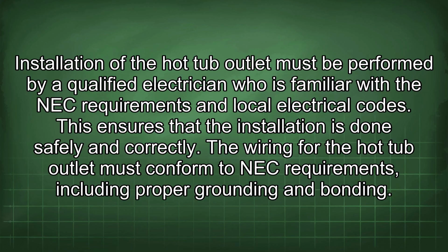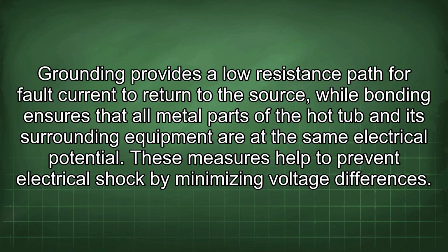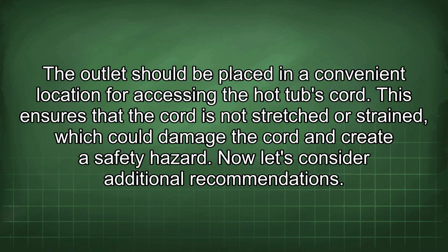The wiring for the hot tub outlet must conform to NEC requirements, including proper grounding and bonding. Grounding provides a low resistance path for fault current to return to the source, while bonding ensures that all metal parts of the hot tub and its surrounding equipment are at the same electrical potential. These measures help to prevent electrical shock by minimizing voltage differences. The outlet should be placed in a convenient location for accessing the hot tub's cord. This ensures that the cord is not stretched or strained, which could damage the cord and create a safety hazard.